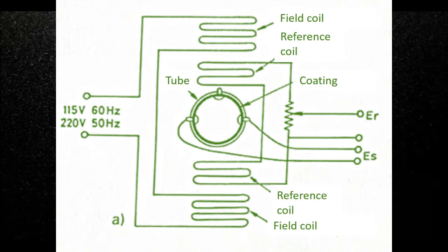These three factors are difficult to keep constant, since the temperature and conductivity of the fluid are determined by the service conditions. Therefore, the voltage signal from the meter is compared at the receiver with another voltage called the reference voltage. Both are derived from the magnetic field. Line voltage and variations in temperature and conductivity do not influence the precision of the measurement. The reference signal is taken from a winding placed in the field windings that generates the magnetic flux. In this image, we can see the connections of the measuring element.